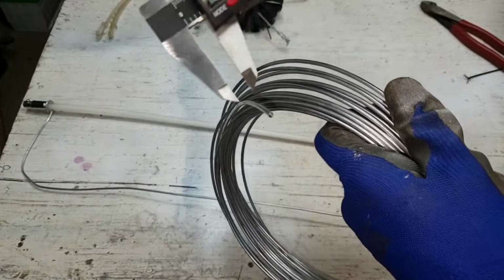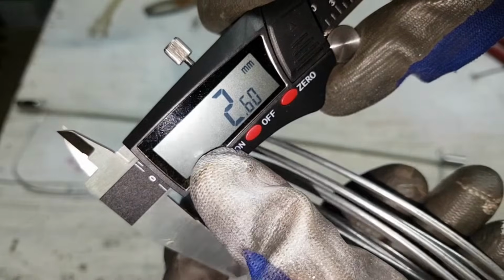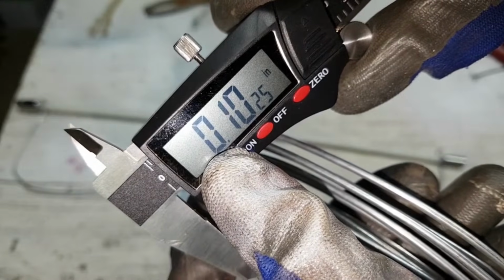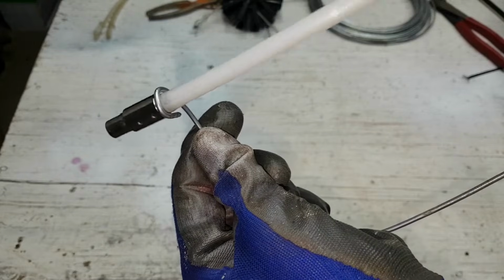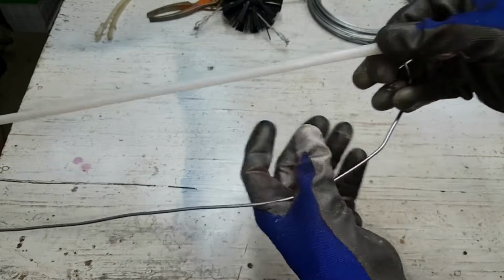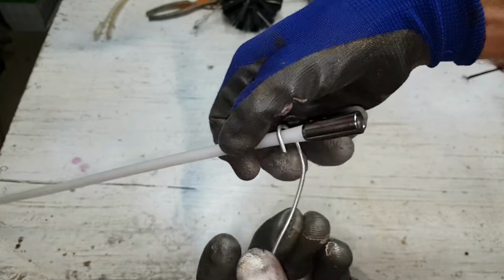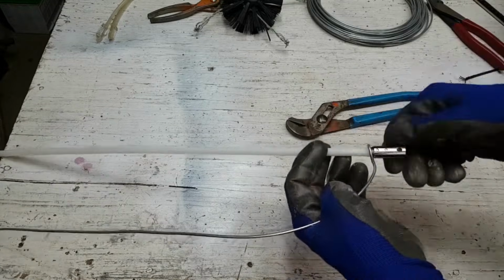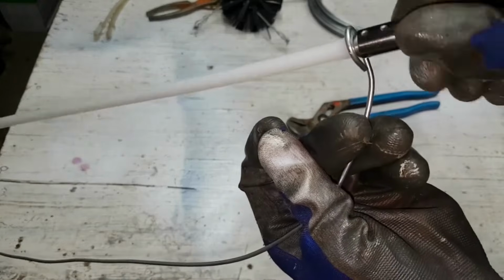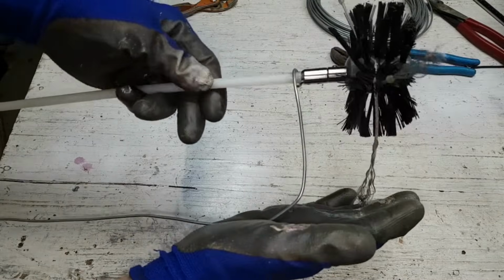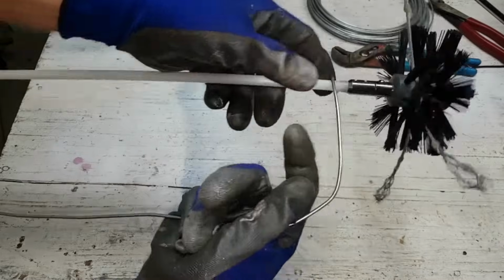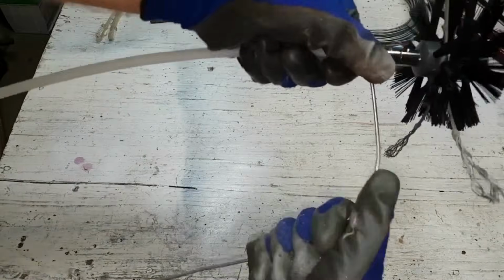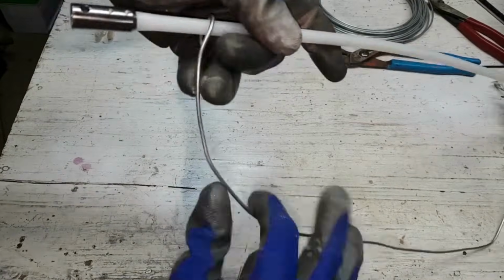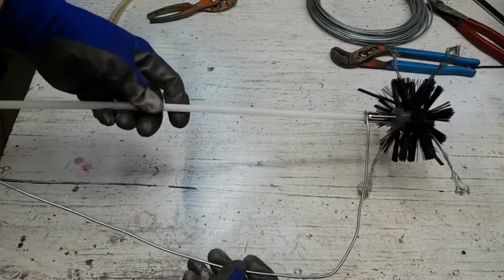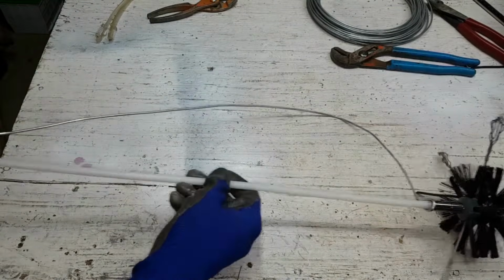Now I need to somehow direct the brush to the center. Got some 2.5 millimeter thick wire here, and I'm going to use it to make a guide for the brush. I loosely loop one end around the rod, then cut the wire to the length I need to loop it around the other end of the rod, like this. Should spin freely. With this tool, I can position the brush wherever it's needed from side to side in the duct. To adjust its position, I simply bend the wire. When I finish one half of the heating duct, the guide will be flipped and I'll clean the other half.